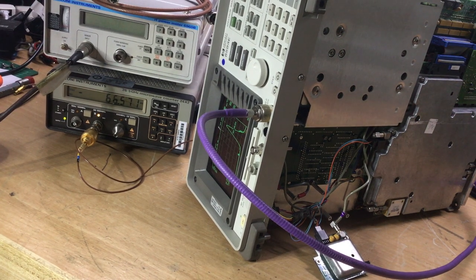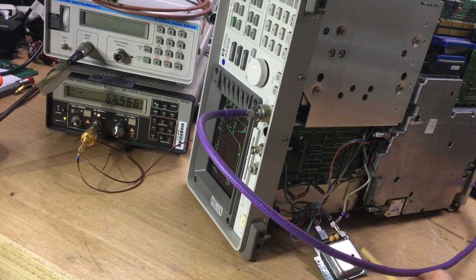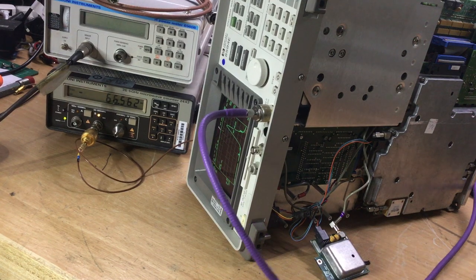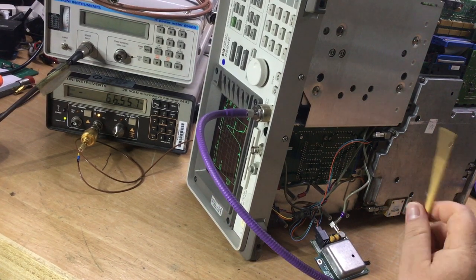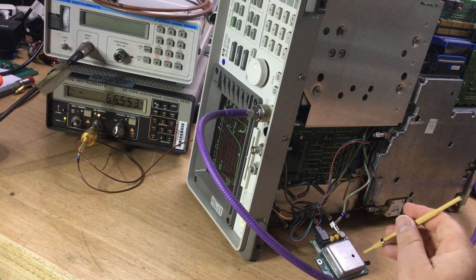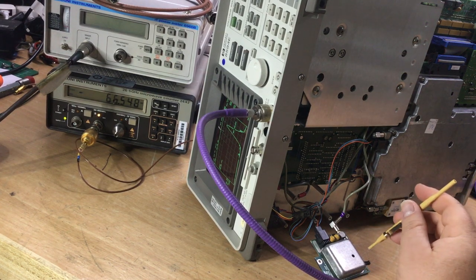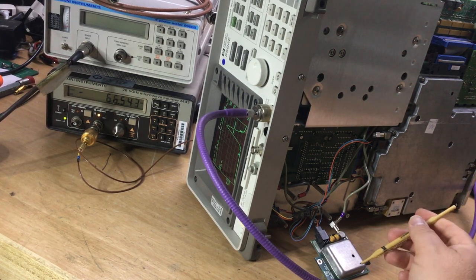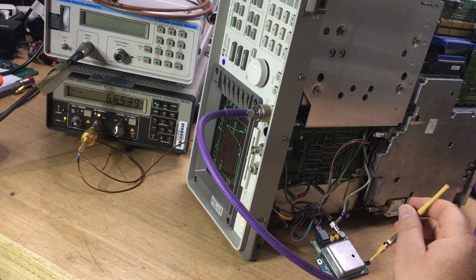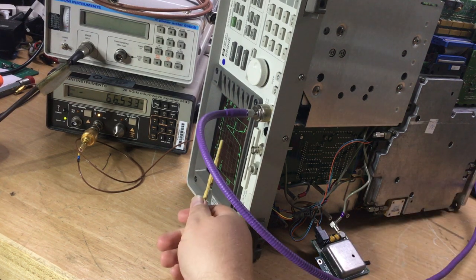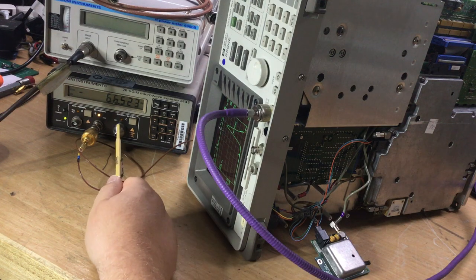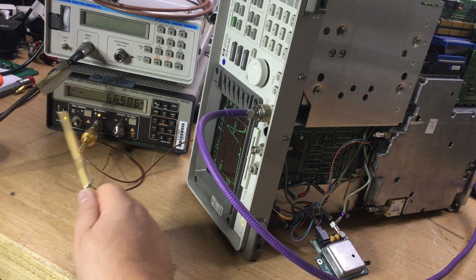Right, so we've got the 10 megahertz oscillator disconnected from the instrument. I've had to undo the screws to get it out. So let's just see what we can do now with that frequency. Bear in mind, of course, this needs to be right in the middle of the screen, and that really needs to be reading as close to zero as possible, so that we know that the 600 megahertz frequency is correct.